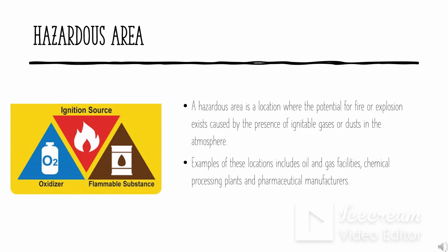What is an explosive atmosphere? An explosive atmosphere is defined as a mixture of flammable substances in the form of gases, vapors, mist, or dust with the air under atmospheric conditions. Atmospheric conditions are commonly referred to as ambient temperatures and pressures, that is to say, in the temperature range of -20 degrees Celsius to +40 degrees Celsius, and within the pressures of 0.8 to 1.1 bar.